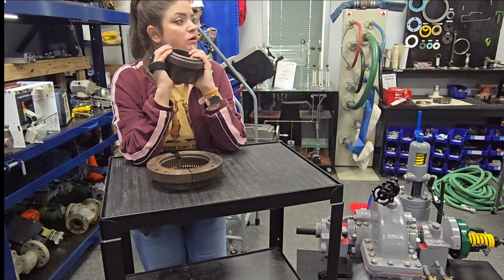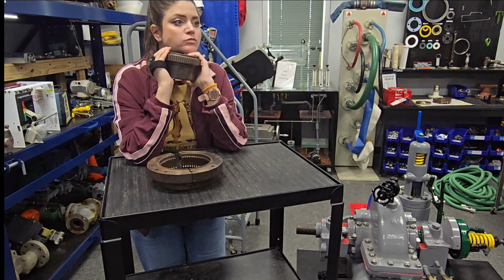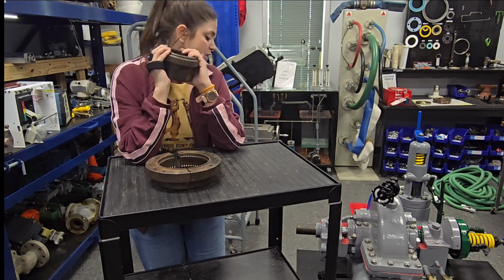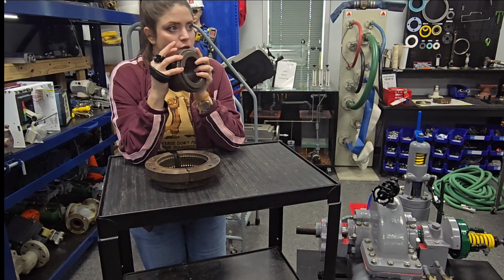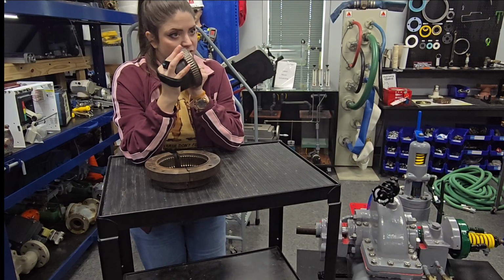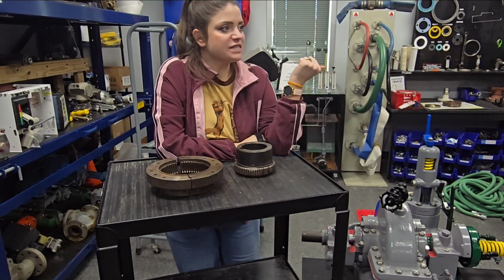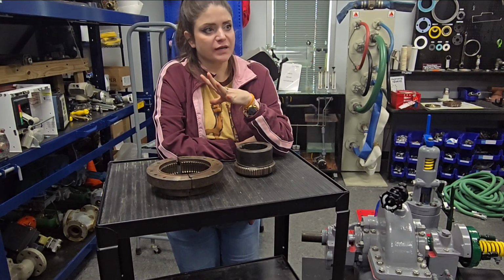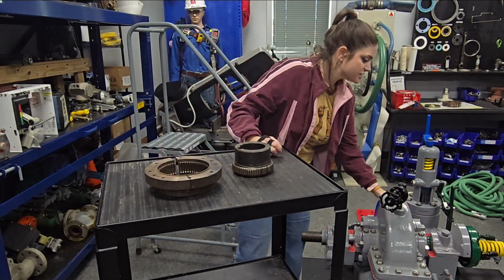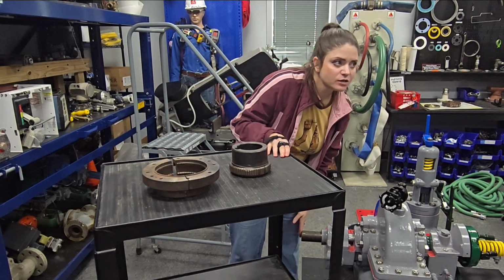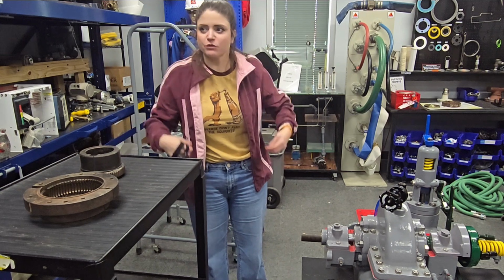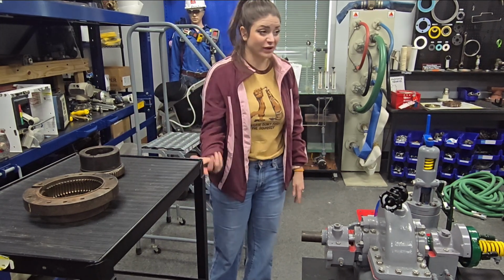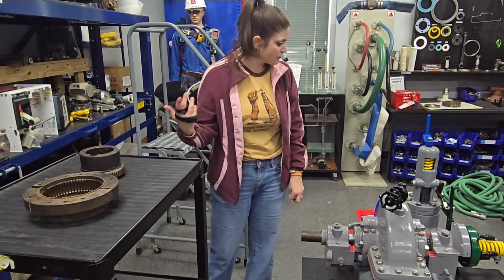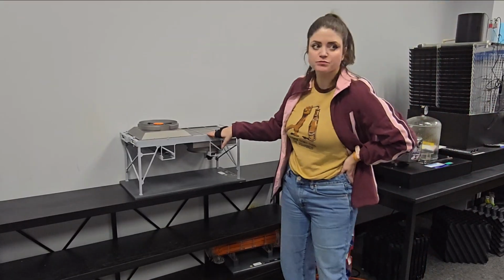Because if that broke, you're only spinning the driver itself. Yeah. So if your coupling broke or shredded, this would be an example of it shredded, the teeth being shredded. There's no resistance from what's being driven. Now the steam's just turning this, right, to here. It's not doing anything and it's not driving anything. So there's no resistance, so it's gonna start going way faster, right? Hence the overspeed trip.